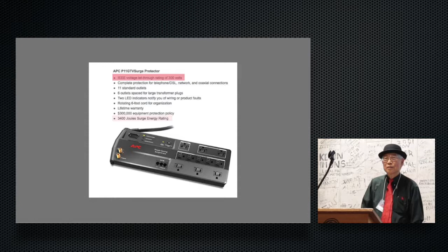MOV devices are generally used to clamp the spikes. They're a weird device. When you put a certain voltage above its rating, it conducts like a short circuit, and then it's sacrificial. It burns up part of itself, and the more pulses applied, the more it burns up and the smaller it becomes.